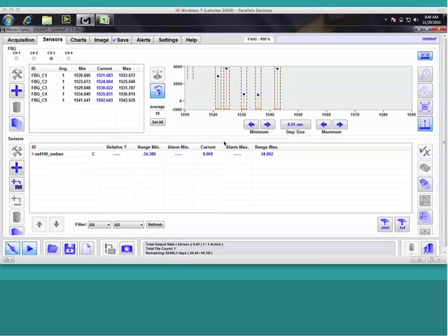One thing I'd like to point out that I've seen happen to users that are creating their configuration offline is you can create sensors offline when you are not connected to the system. If you do, when Enlight attempts to take a snapshot of your FBG, of course you're not connected to the instrument, so they have no value. What will happen is Enlight will take the center of the FBG bin as the reference value, and then once you do connect to your system, what can happen is you'll see a large value for the measured result.